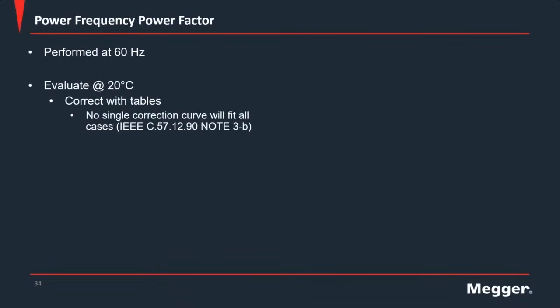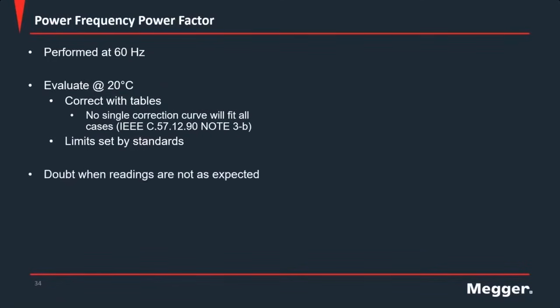But insulation power factor never improves from the time that the bushing leaves the factory. So it's always going to get worse. And if we know that it's always going to get worse, then we know that the temperature correction tables won't necessarily work for all cases. But it is the standard practice today, so we correct with the tables, and then we look at the limits set by the standards, which you saw on the previous slide. But there is a lot of doubt when readings are not as expected.